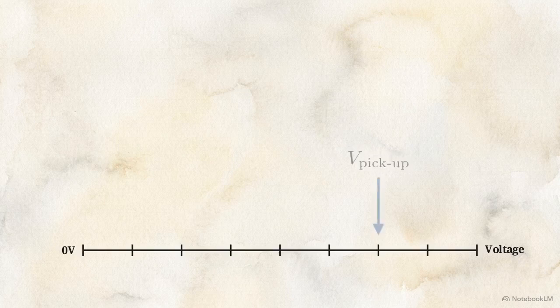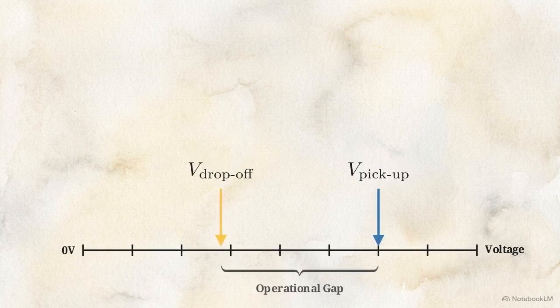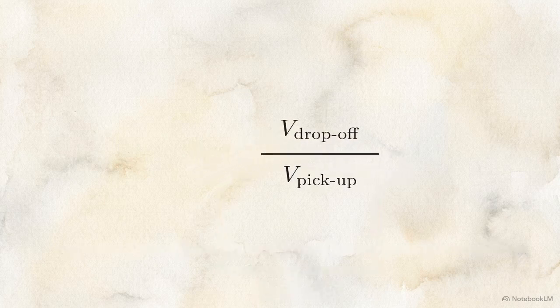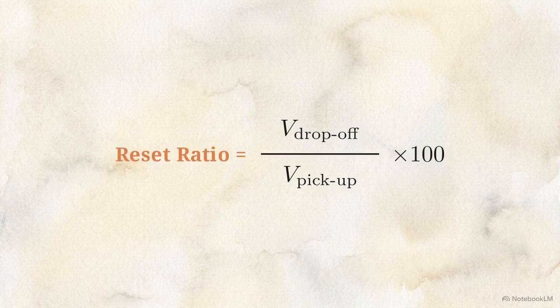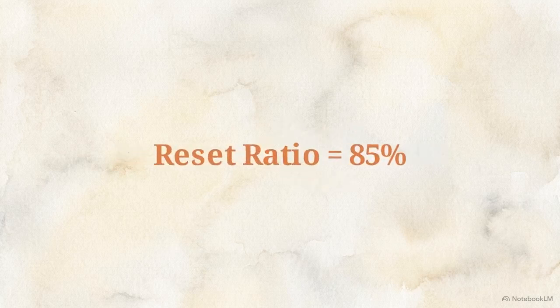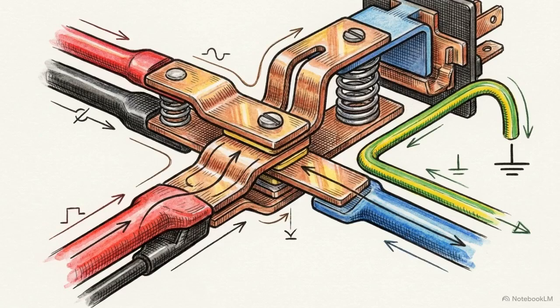This animation shows the formula for calculating the reset ratio. Engineers divide the drop-off voltage by the pickup voltage and multiply by 100 to determine the operational health of the relay. Verifying these exact timings and reset ratios guarantees that the board's nervous system responds accurately to control signals, with no logical errors.